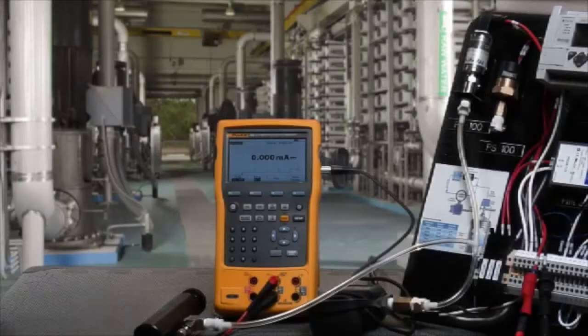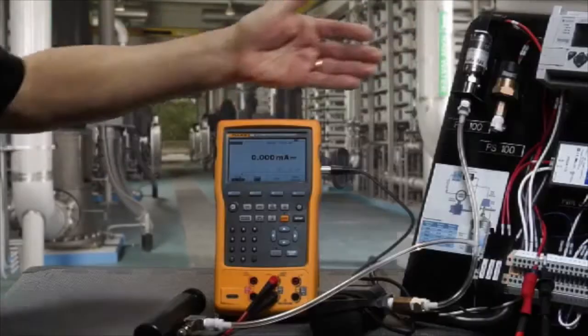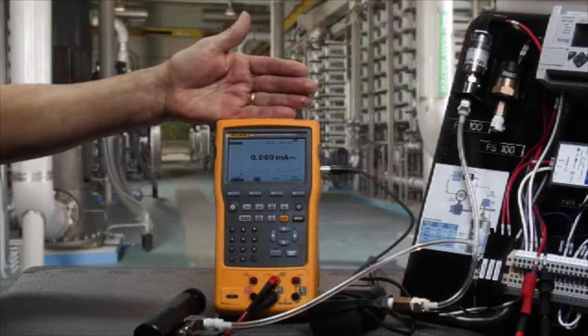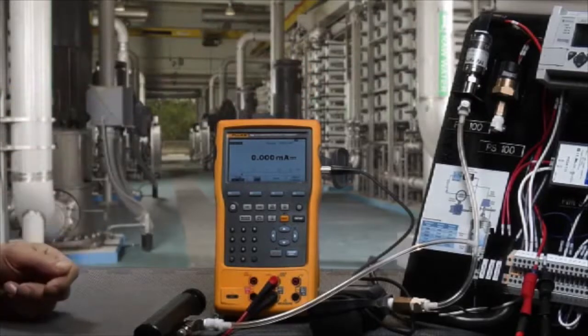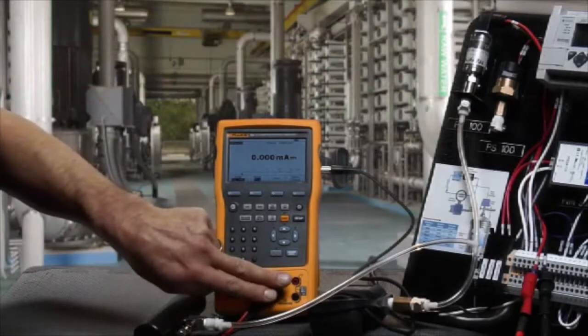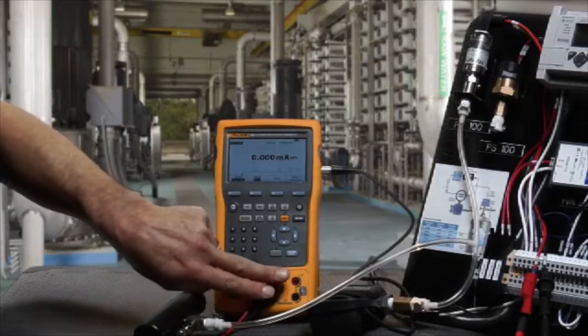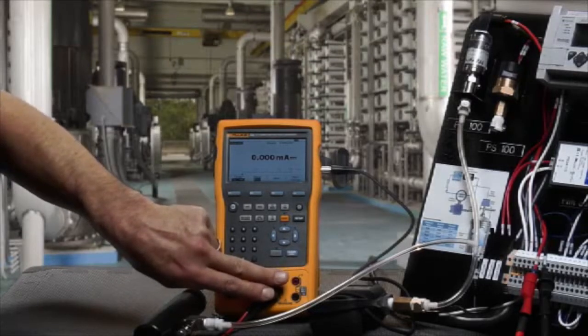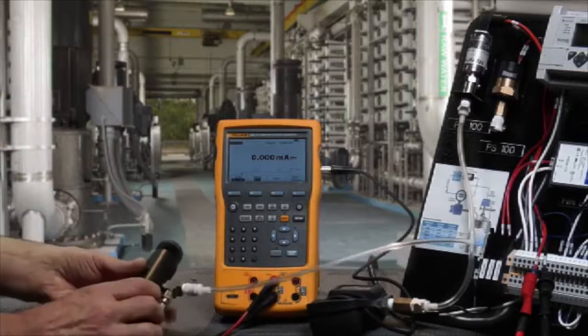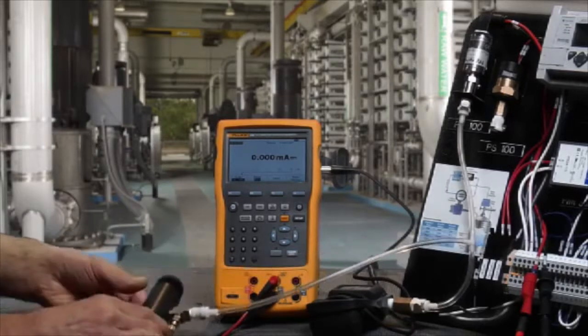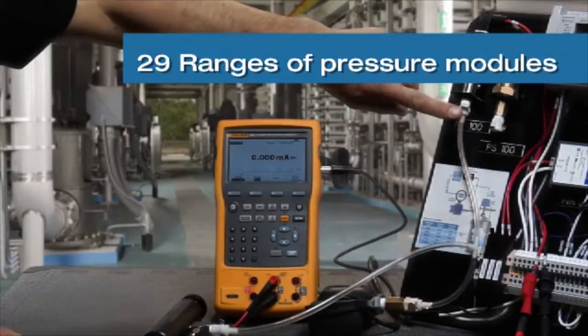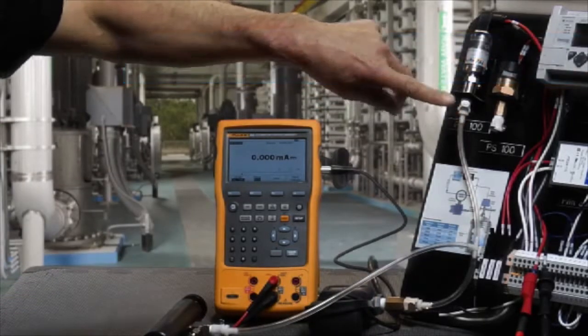Let's go through how to calibrate a pressure transmitter using the Fluke 754 documenting process calibrator. In this example, we're going to measure the milliamp signal drawn by the pressure transmitter as well as powering it with the internal loop power supply. We're going to generate pressure with the hand pump into the Fluke pressure module, which is also then connected to the input of the pressure transmitter.